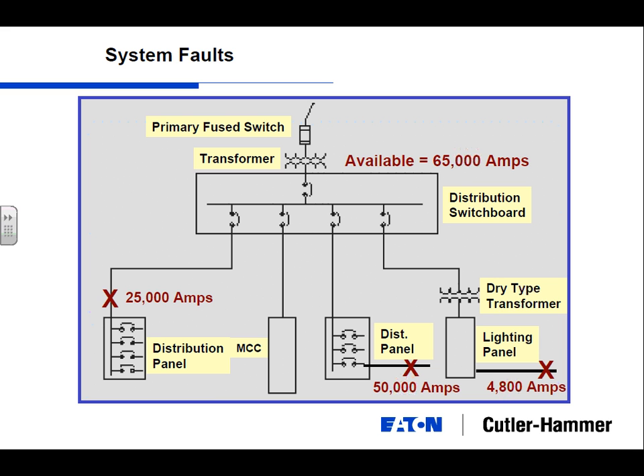And historically, they've done that. So they are doing more and more of handing the customer 15 kV or a higher voltage, so the customer has to come in, take the 15 kV, put in their own transformer to step it down to 480 and use it, and then the customer ends up eating that money. So that's a very real industry question right now.